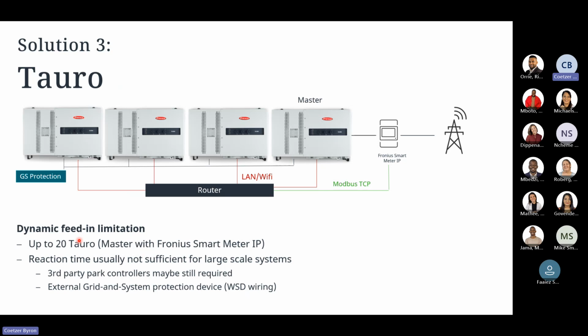Again, the reaction time is usually not sufficient for large scale systems. So if we are doing systems where it is 2 megawatts, for example, a third party controller may still be required regarding the reaction time if we have loads that fluctuate quite heavily. As well, using external grid and system protection devices, such as using your WSD wiring for this configuration, is recommended.